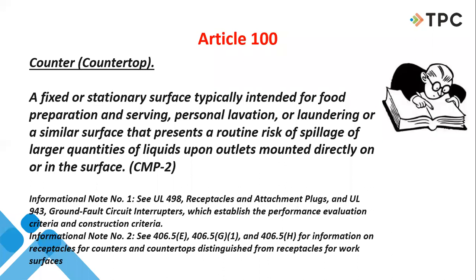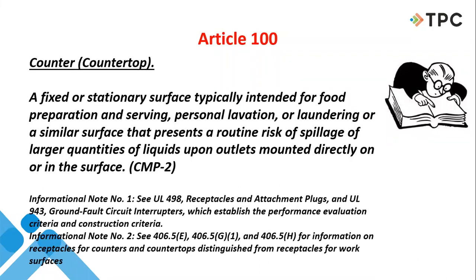Well, a countertop, by definition now, is a fixed or stationary surface, typically intended for food prep, serving, laundering, or similar service that presents a routine risk of spillage of large quantities of liquid. Well, if that's the case, in fact, they directly refer to them. The spillage of liquids would be upon outlets mounted directly on or in the surface. So some of these specialty receptacle arrangements that we've all seen or dealt with, the ones that pop up out of the counter, have a seal that will protect spillage from getting down into the recesses where these receptacles are mounted. This is what some of these more specific definitions are geared toward.